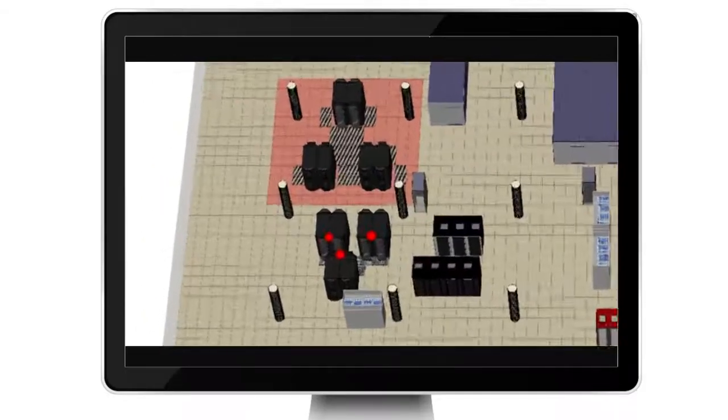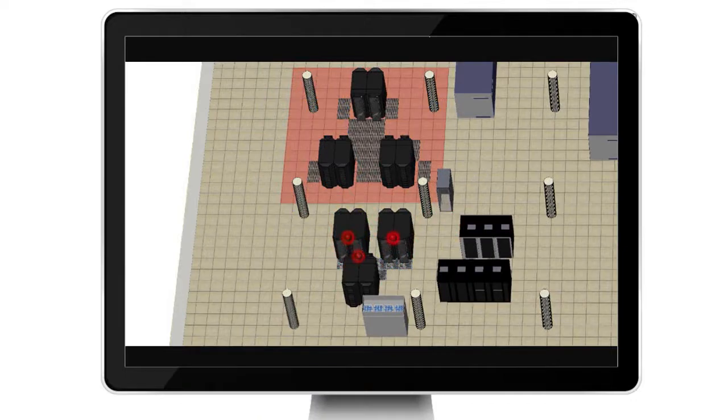After a simulation, digital twin reveals something that we didn't know before. The most likely selected option will fail compliance by overheating existing IT racks. Digital twin's ability to mimic physical behavior helps avoid this unexpected compliance disaster. It also reveals the cause of the compliance problem and provides the foresight needed to design a solution. A new cooling unit will eliminate this violation, but at an unexpectedly high cost after factoring in the impact of the new cooling unit.